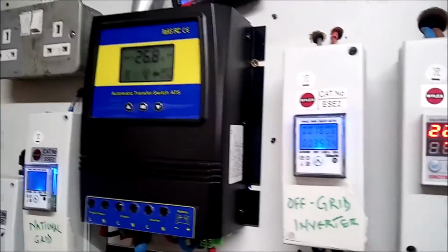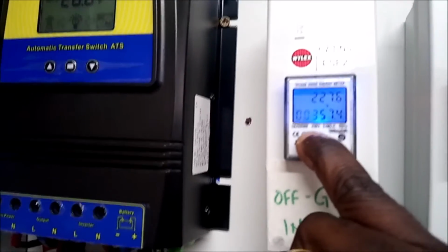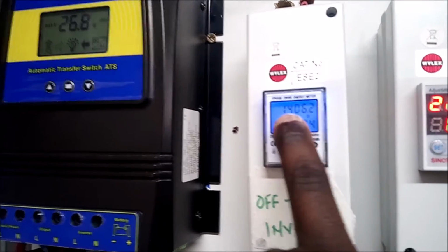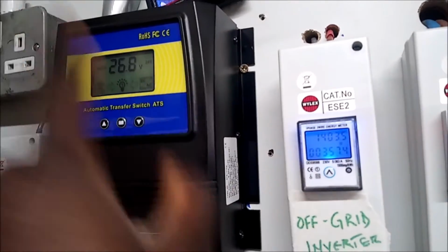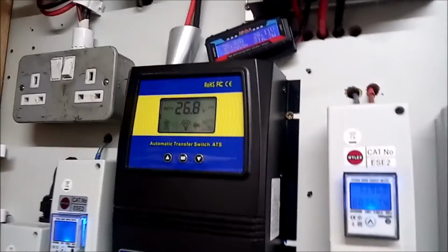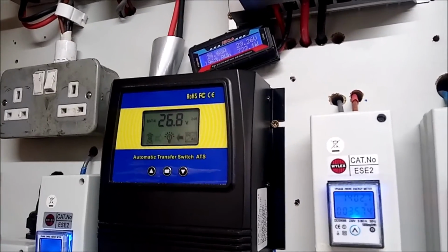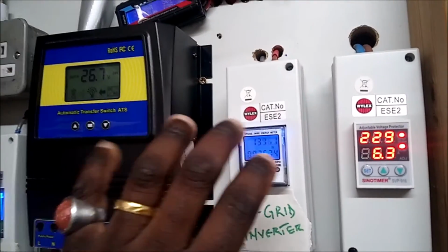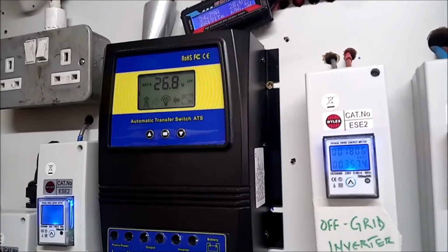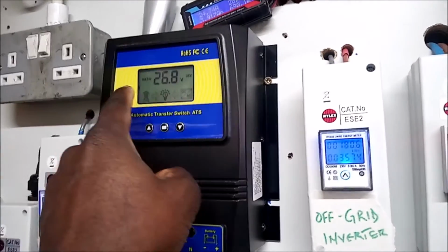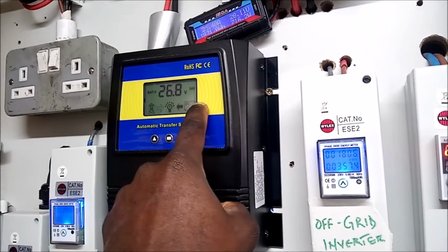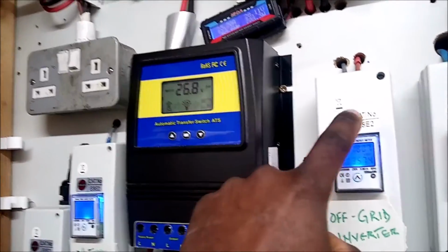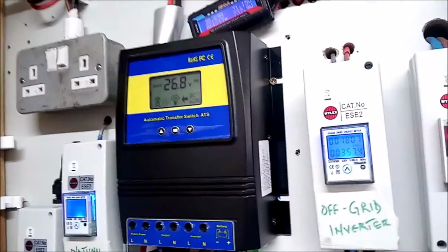Now, having said that, I am currently pulling 1.4 kilowatts, that's 1,400 watts, which means I'm already exceeding the 1,200 watts they said I shouldn't exceed. I think where it's going to go bad is when the voltage goes down and it switches over to the national grid. That's what I suspect. I've never tried that because I don't want to damage it. If you switch back to the inverter while you have about 1.3 or 1.4 kilowatts as I have right now, it may damage it. That is what I suspect.